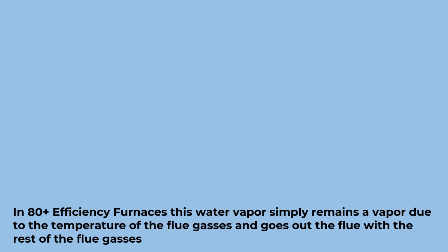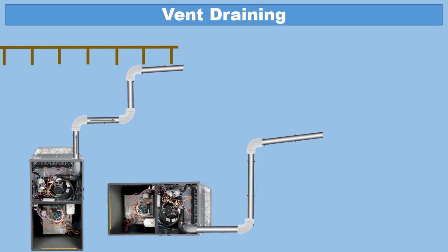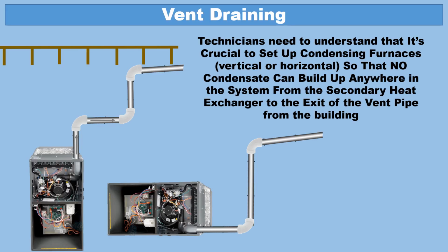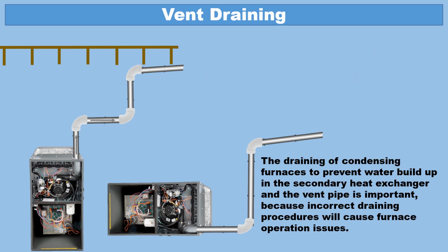In 80+ efficiency furnaces, this water vapor simply remains a vapor due to the temperature of the flue gases and goes out the flue with the rest of the flue gases. Technicians need to understand that it's crucial to set up condensing furnaces vertically or horizontally so that no condensate can build up anywhere in the system from the secondary heat exchanger to the exit of the vent pipe from the building. The draining of condensing furnaces to prevent water buildup in the secondary heat exchanger and the vent pipe is important because incorrect draining procedures will cause furnace operation issues.